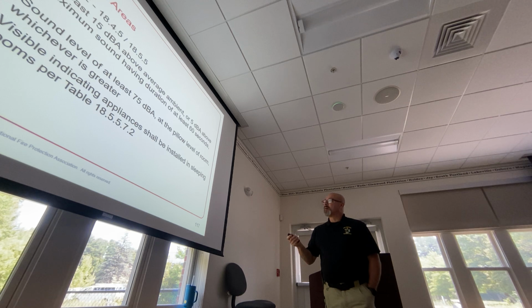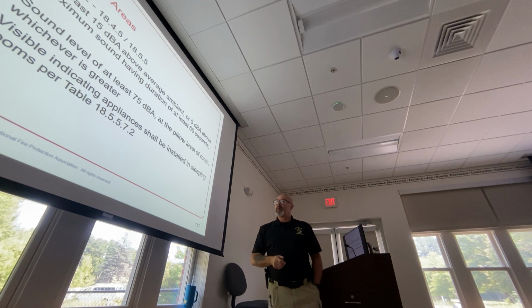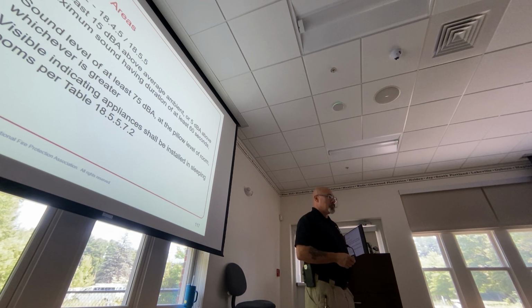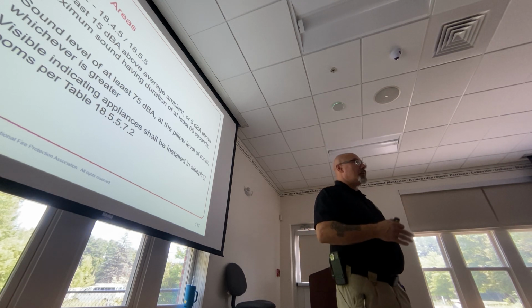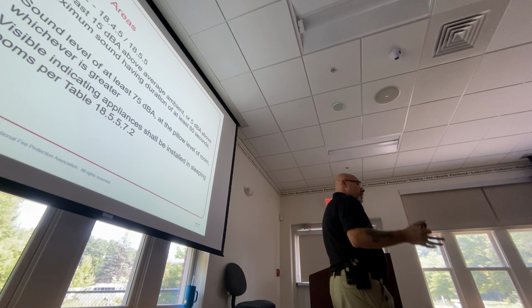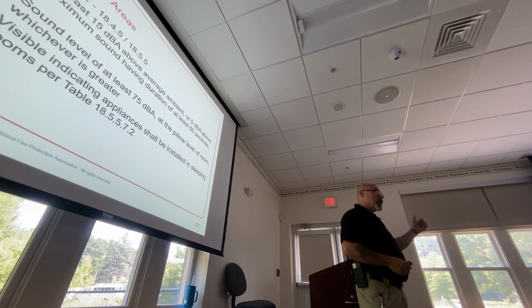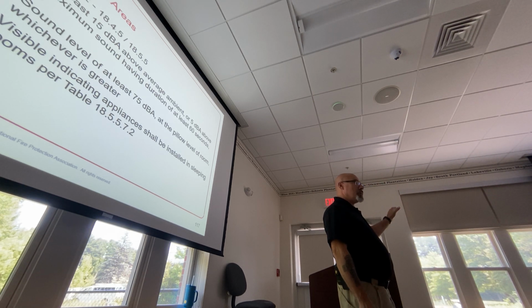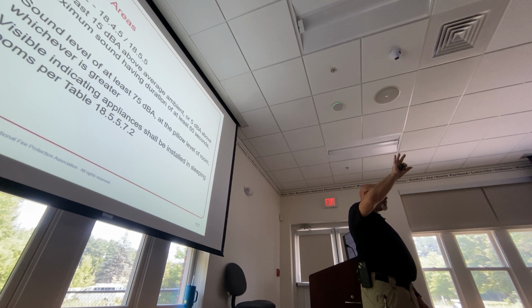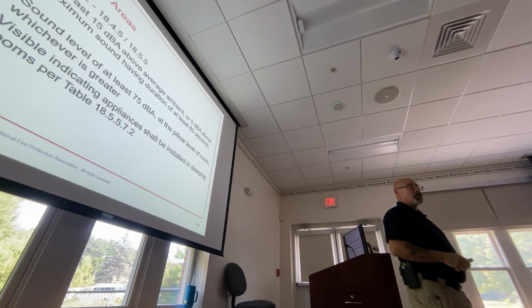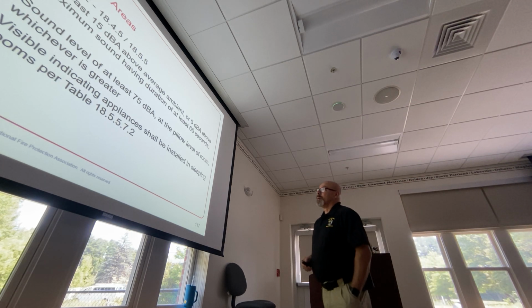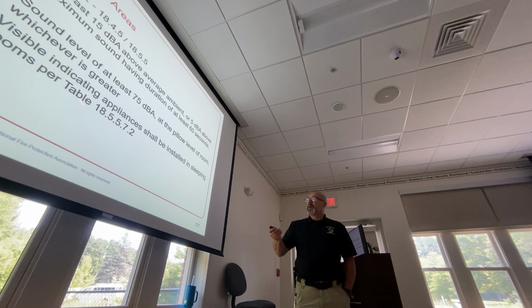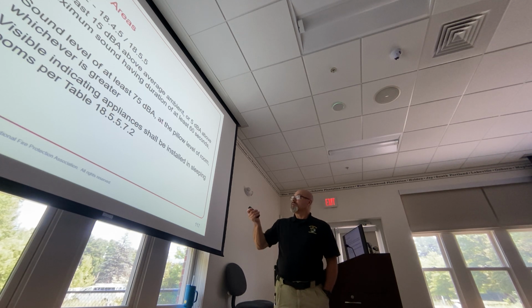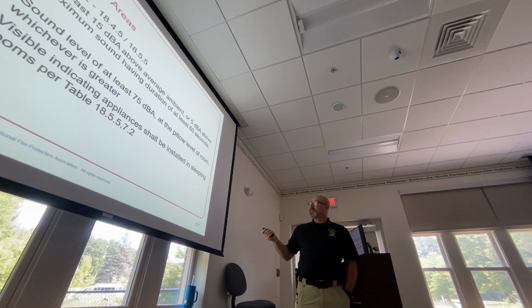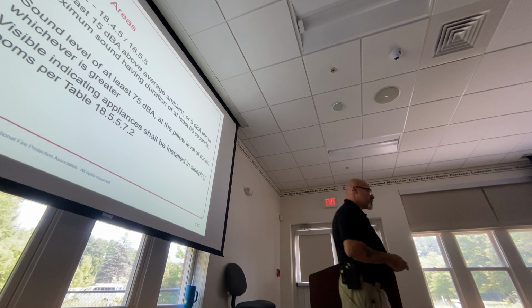So visible indicating appliances shall be installed in sleeping rooms per table 18.5.5.7.2. Anybody that's ever been in a hospital room and the alarm's going off, you might not hear anything other than that one ding, code red. And then you'll have your visible appliances, your strobes going off. But 18.5.5.7.2 tells you that, and you may see this question on the test.